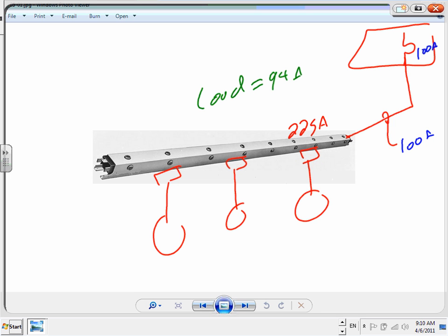That's fine. So my point is, if you know your load is small, but 225 amp is the smallest that you can buy, then it might be a good idea, especially with a difference like this. Look at that, 225 amp to 100 amp. That's almost double. So it might be a good idea to size it based on the overcurrent protection device. The next overcurrent protection device is 100, and the cable is 100. Call it a day.